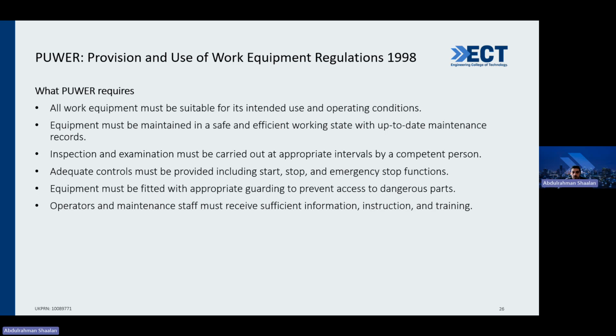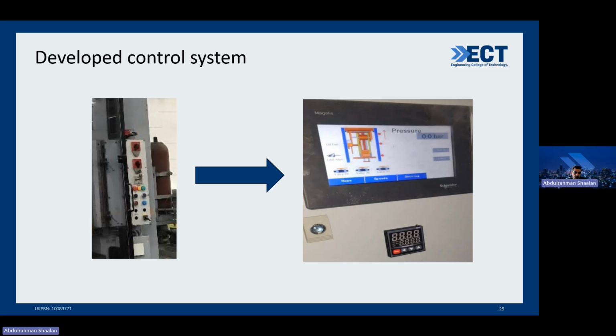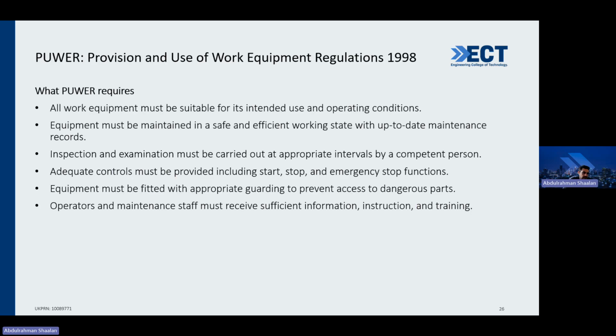Adequate controls must be provided, including start, stop, and emergency stop functions. These are the basic, main requirements. We added the ability to start the cycle from the screen, which is easy and possible, but PUWER states you must also have physical buttons. This is basically a redundancy element, to make sure that if anything goes wrong with the screen, you have that physical button which is more rigid, to avoid any incidents.